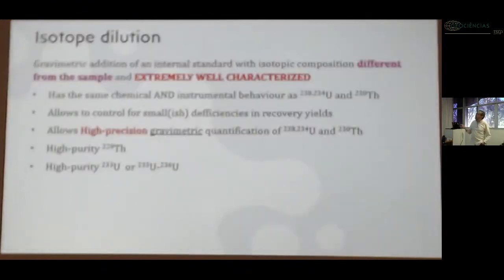When I mean that they are extremely well characterized, they have to come with some kind of certificate like this. These are the certificates for the spikes that I have for thorium-229 from Oak Ridge National Lab. It has to give you a little bit of an idea of how many of the thorium isotopes are present and their abundance. For the 233 spike that we have, it also has to give us an idea that it's mostly uranium-233.